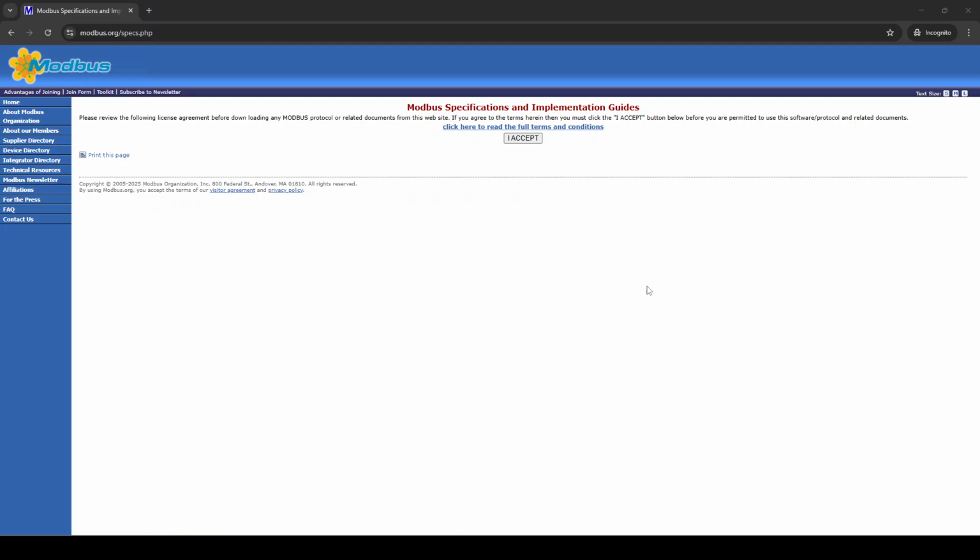And when we talk about Modbus RTU, we are usually referring to Modbus running over an RS-485 network. In this setup, the devices communicate using a master-slave architecture. The master sends a request and the corresponding slave device responds. Each device on the RS-485 bus has a unique address, and only one device can speak at a time to avoid collisions. This setup is simple, reliable, and cost-effective, and that's exactly why it's still so popular today, Modbus.